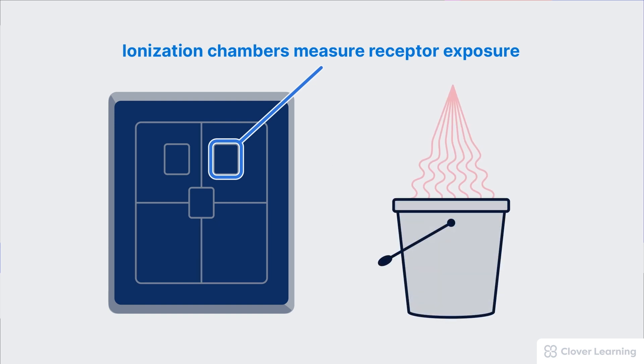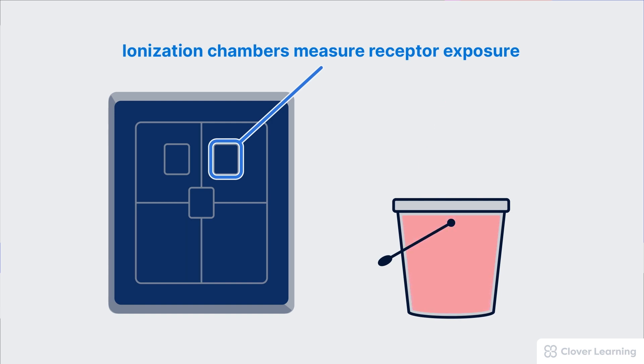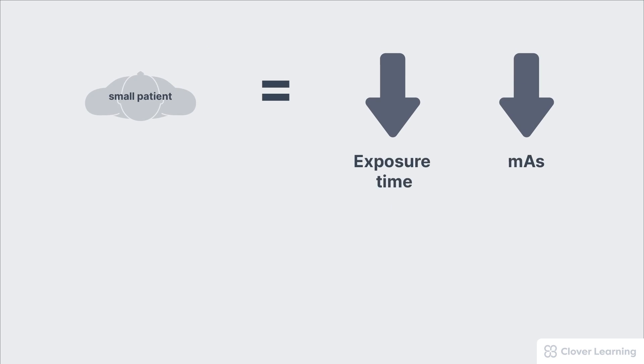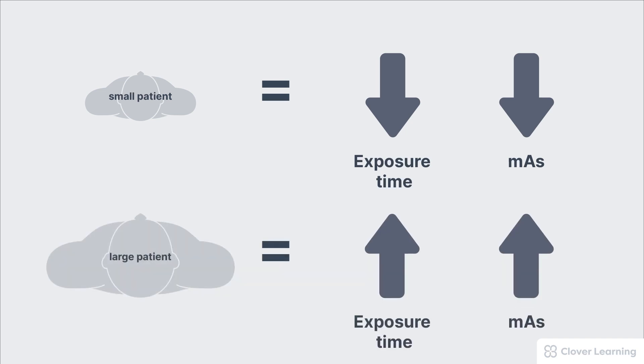Think of these ionization chambers as buckets. These chambers collect radiation during the exposure, and once the bucket is full, the exposure shuts off. Exposure times can vary widely depending on the patient size. For small patients and small parts, the AEC system will shut down the exposure sooner, resulting in a shorter exposure time and a lower mAs — which is exactly what we want for a smaller patient. For larger patients and larger parts, the AEC system will extend the exposure time longer, resulting in a larger mAs, and that's exactly what we want.